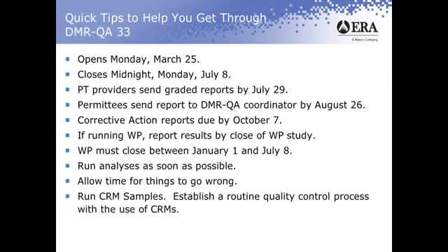One of the other things I'd like to emphasize and stress is to run the certified reference material samples. As Rick had mentioned, certified reference materials are samples of a known value where you're going to receive a certificate of analysis for that known value. On that certificate of analysis, not only are you going to get the value of the analyte that you're looking for, but you're going to get what we call quality control limits, or performance acceptance limits, from ERA.